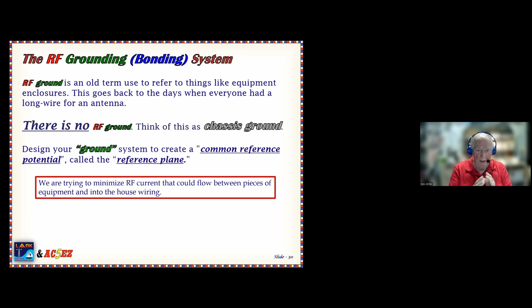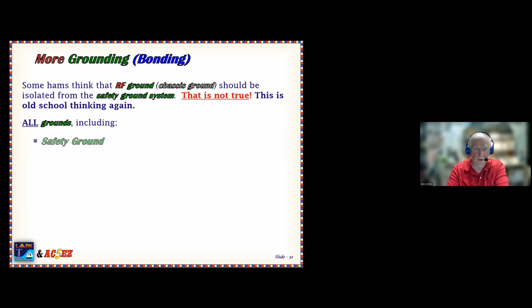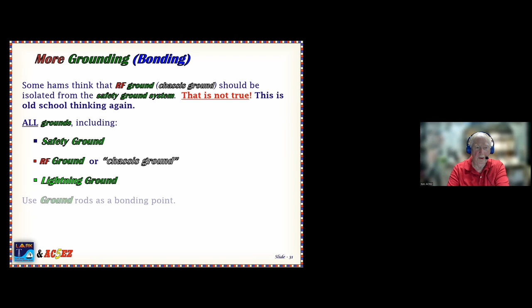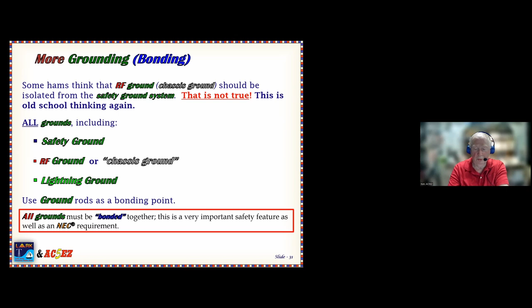All right. Some hams think that RF ground should be isolated from the safety ground in the house. That is an absolutely not true statement. This is old school thinking. All grounds, now I say all grounds, including safety ground, your chassis ground, your lightning ground, all grounds must be bonded together in order to make one ground point. And this is explained in the NEC. It's a requirement that all systems be grounded to a common reference potential.